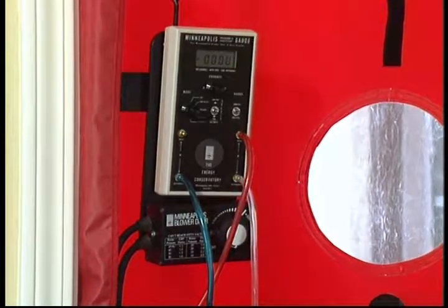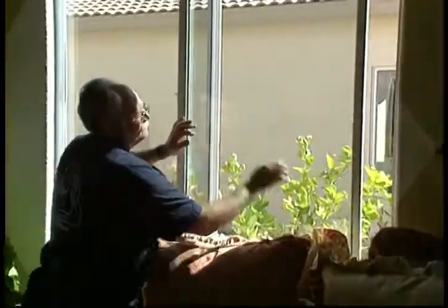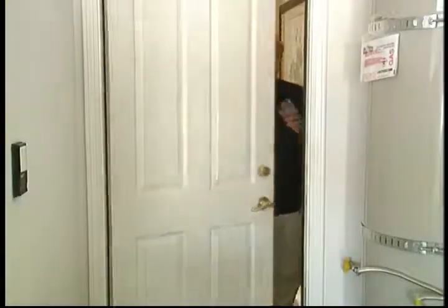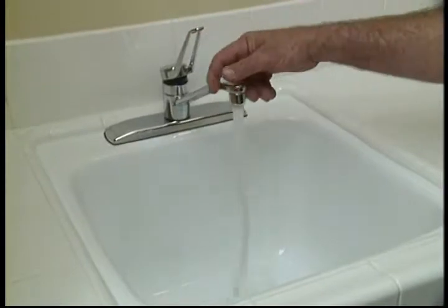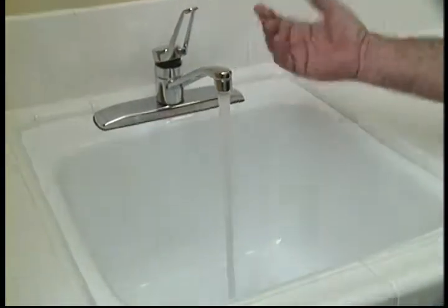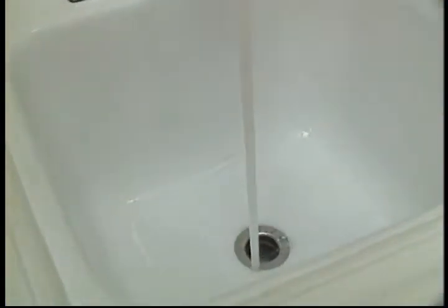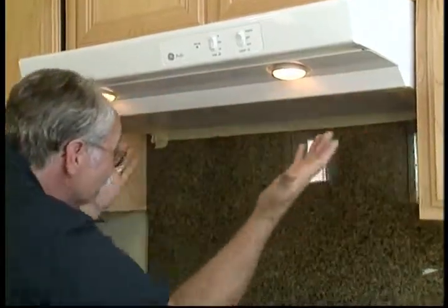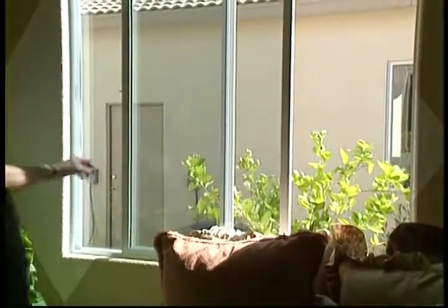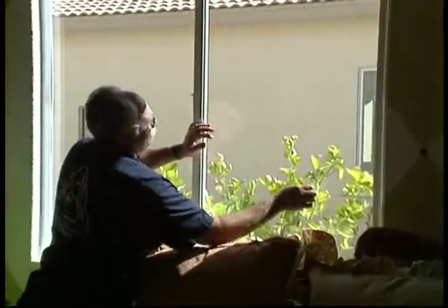When I come out to the house, Steve, I walk around and familiarize myself with the house, and then I start preparing the house for the test itself. Make sure that all the exterior windows are closed, all the exterior doors are closed, all the interior doors are open because we want to measure every room, the whole house. And I check plumbing traps to make sure they're full of water. And any exhaust fans that have dampers, I make sure that they're closed off. Because we want to prep the house for its normal operating conditions.